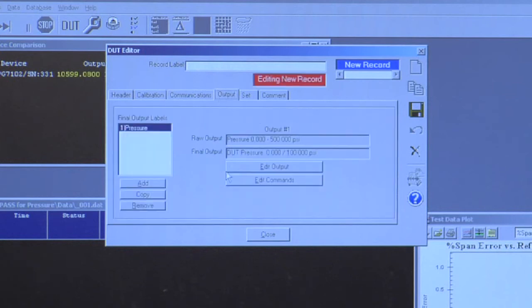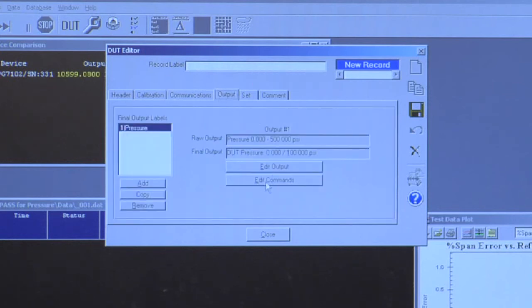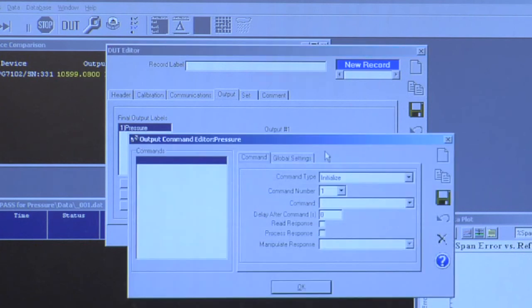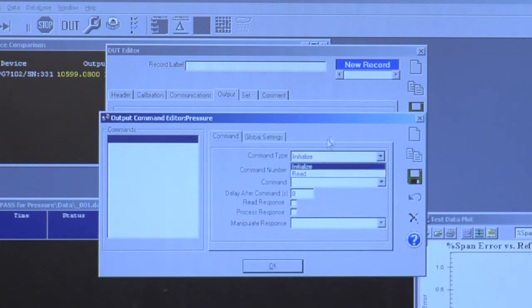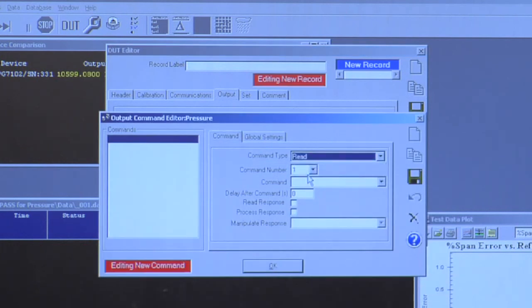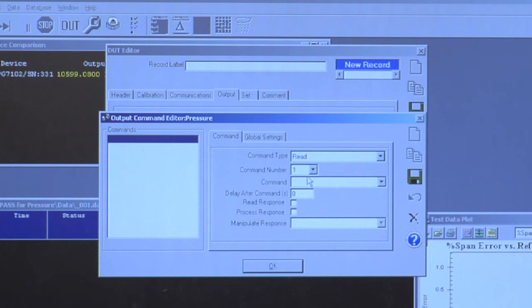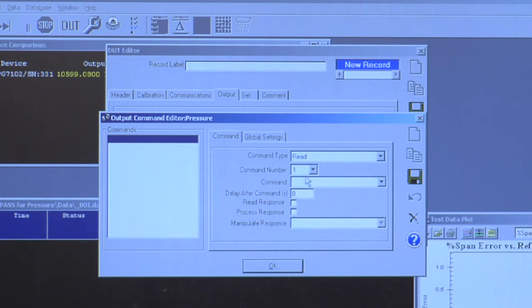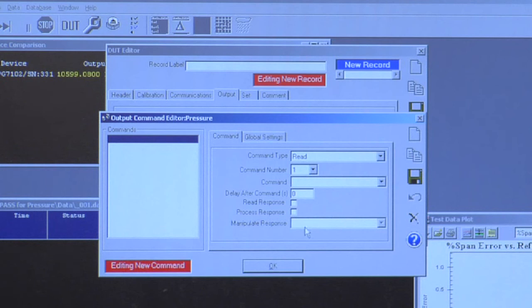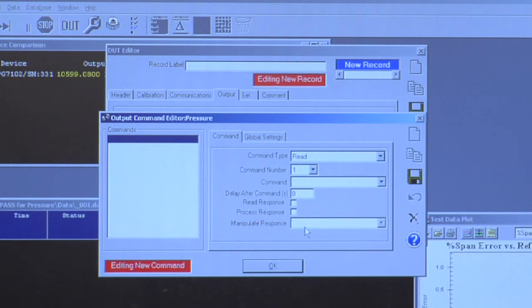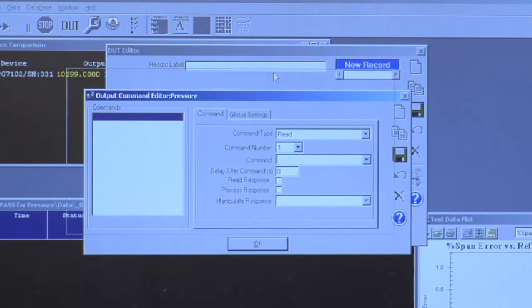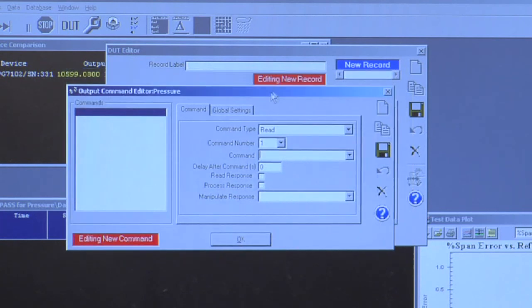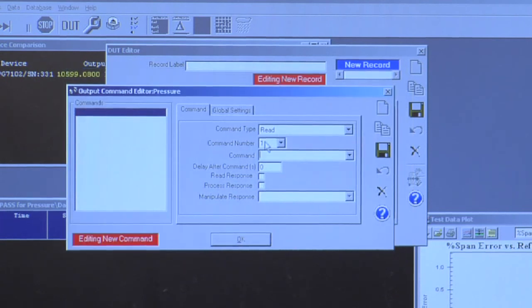More importantly, though, I can define all the specific remote interface commands for IEEE. So if I choose Edit Commands, I can create as many commands as I want to read this instrument. So each command, I can parse the response to get a specific quantity that I can use while the test is running. So using this combination of features, I can use just about any host instrument that has a supported interface.